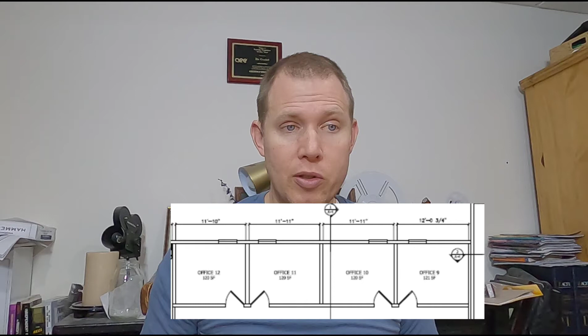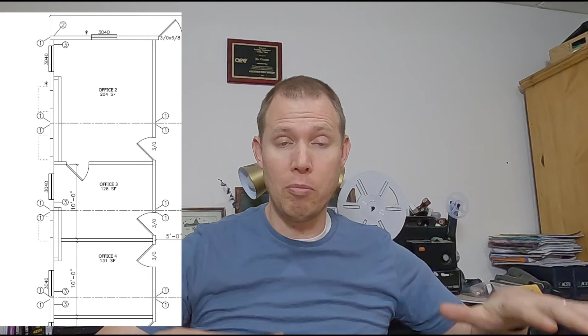Let's look at a second scenario where you have two rooms and one of them is twice as big as the other. Now, as long as the loads are proportional, in other words, if the bigger room has twice as many lights as the smaller room, twice as many people, computers, etc., if everything is proportional, then you would be able to just put twice as much cooling into the second room and they'd still move together. They still follow the same loading pattern.